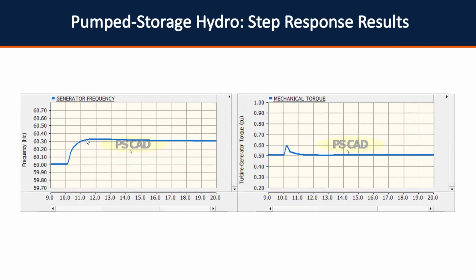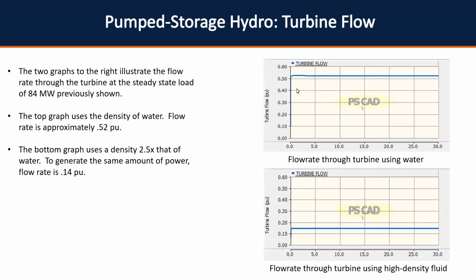I think this system response is a little slow compared to other step response tests I've seen done for real generators. The problem was the mechanical torque spiked so hard with that gain on there. I was trying to limit that to something more reasonable. I don't have a point for equipment failure or design limitations, but I try to keep it within reason. As a result, my frequency response was a little slow. Somebody who specializes in governor tuning could probably get this down a little better, but that's what we got.